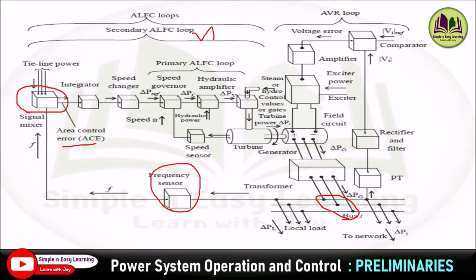The secondary ALFC loop is a very slow process. Since the frequency is sensed, compared, and sent to the speed changer, this loop is insensitive to rapid load and frequency changes. Instead, it focuses on drift-like changes that take place over a period of minutes. Using both the primary and secondary ALFC loops, speed is controlled, which in turn controls the frequency of the system, since speed is directly proportional to frequency. This variation of speed results in variation of real power.